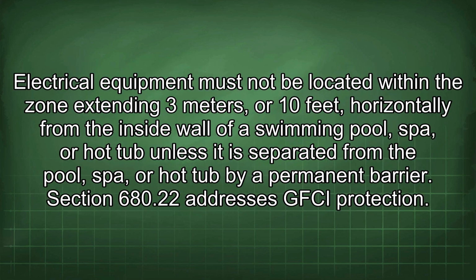Electrical equipment must not be located within the zone extending 3 meters or 10 feet horizontally from the inside wall of a swimming pool, spa, or hot tub unless it is separated from the pool, spa, or hot tub by a permanent barrier.